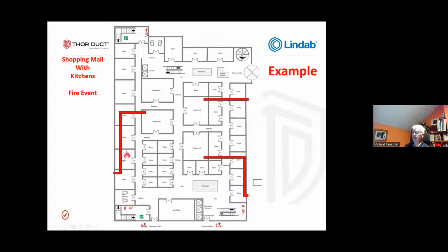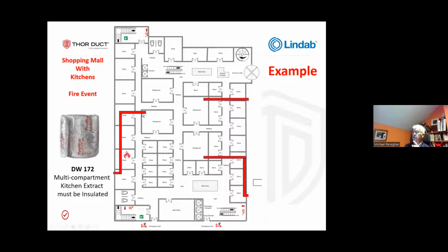The fire starts in another compartment. The result of that fire is it hits the suspended ceiling, goes above the suspended ceiling, and it touches off the kitchen extract. The kitchen extract has grease inside it. It will ignite at 180 degrees. And suddenly there is a danger to our compartment strategy because the fire will break out in every section along the way and back into the kitchen. So that's a real problem. So what we need to do is we need to insulate the multi-compartment element of the kitchen extract as it travels through the building until it reaches the outside to keep the heat out.